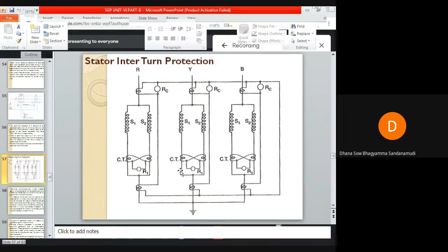Similarly for each phase. Under normal operating conditions, the currents in the stator windings S1 and S2 of each phase are equal. So the currents in the primaries of these CTs will be equal. Hence, the EMFs induced across the secondaries of these two CTs will be equal, and the currents flowing through this loop in the secondaries will be equal and opposite. Therefore no current will flow through this relay R1, and the relay R1 will not operate.